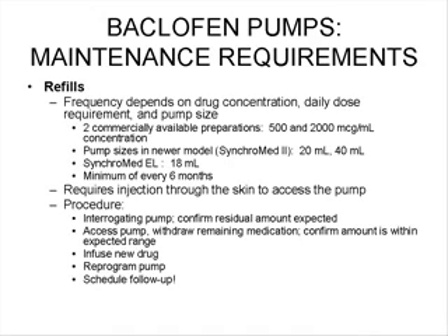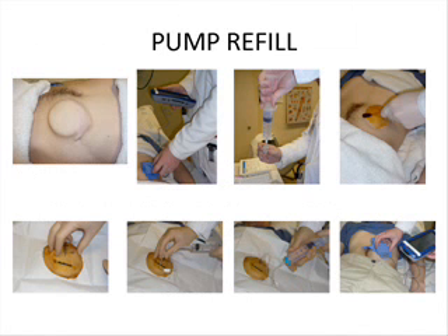And the general procedure is that we interrogate or analyze the pump, and we try and confirm how much we expect to be able to withdraw as residual amounts in the pump at that specific date. We then access the pump with a needle, and we withdraw the remaining medication, and we see if that matches what we expect to get back based on what the programmer tells us we should expect. We then infuse the new drug, reprogram the pump, and the most important part is to not forget to schedule follow-up.